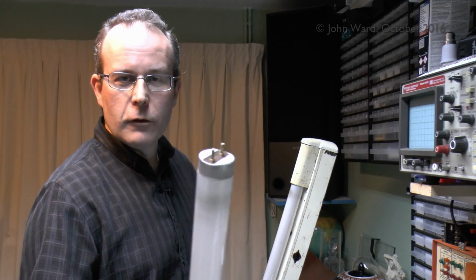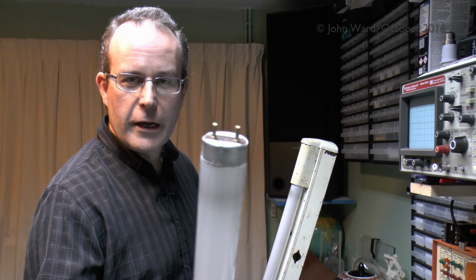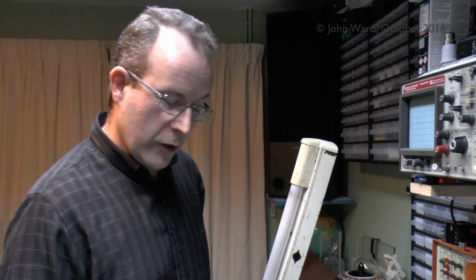If you've got a larger one, like in the background there with the T12 tube, you can in most cases put a T8 tube in as its replacement, because the end connectors are the same, it's just that the tube is physically larger. There are a couple of types of tubes where you can't do this, particularly some of the older ones that have no starter, and also that one in the background, which we'll look at right now. Now, I said earlier that all the tubes have the standard pins on the end, and in fact most of them do, including the old T12 variety.